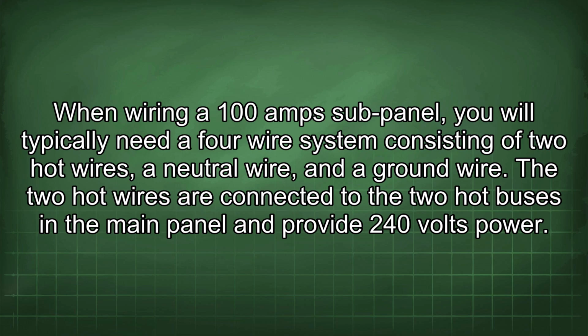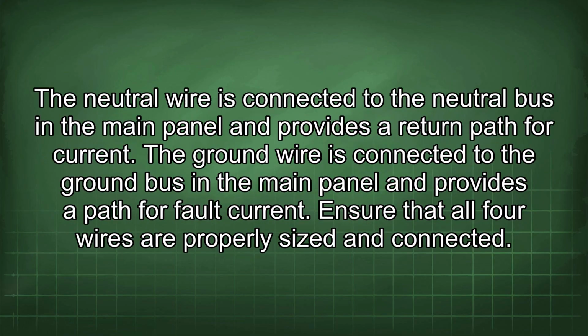When wiring a 100 amp sub-panel, you will typically need a 4-wire system consisting of 2 hot wires, a neutral wire, and a ground wire. The 2 hot wires are connected to the 2 hot buses in the main panel and provide 240 volts power. The neutral wire is connected to the neutral bus in the main panel and provides a return path for current. The ground wire is connected to the ground bus in the main panel and provides a path for fault current. Ensure that all 4 wires are properly sized and connected.